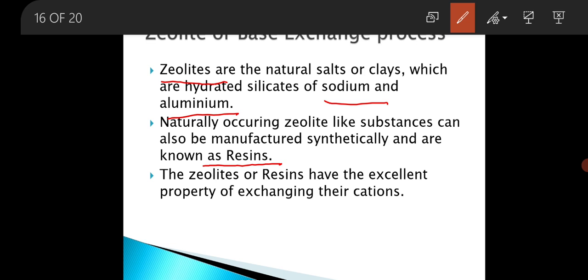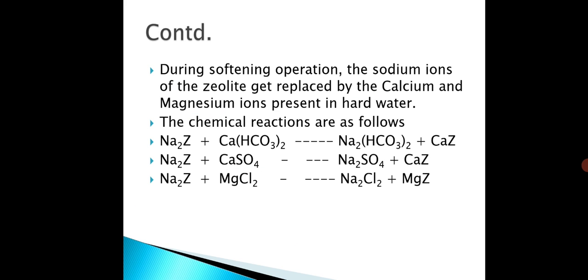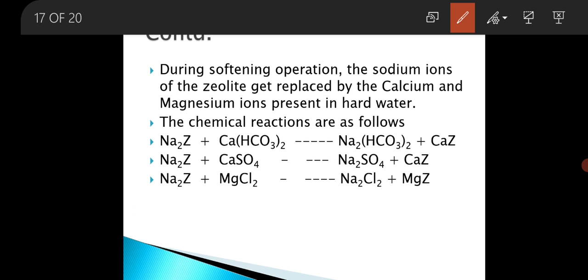These zeolites or resins have an excellent property of exchanging their cations. During the softening operation, the sodium ions of the zeolite get replaced by the calcium and magnesium ions present in hard water.